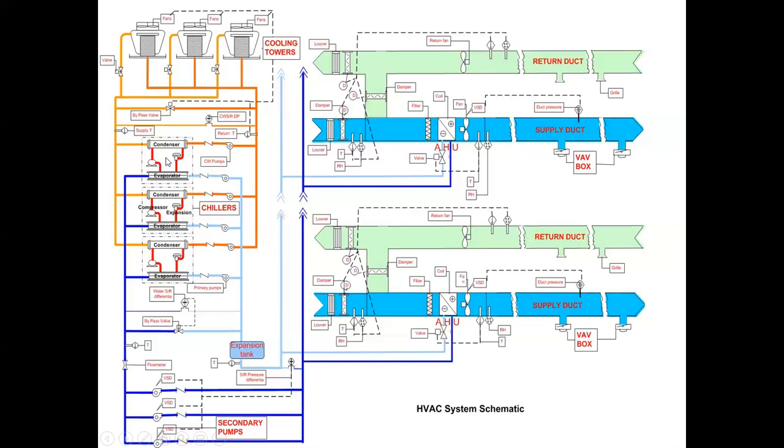It's hot superheated vapor coming out of the compressor. It goes into the condenser. We condense it at high pressure to a liquid. We put it through an expansion valve and drop the pressure. We get two phase, mostly liquid but some vapor, and it's cold because that's what refrigerants do. When they're liquid at high pressure and you drop the pressure, they get cold.